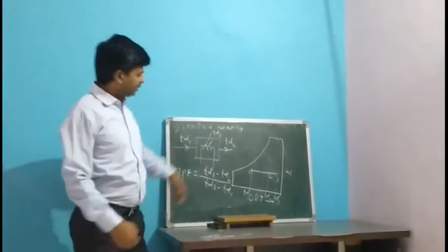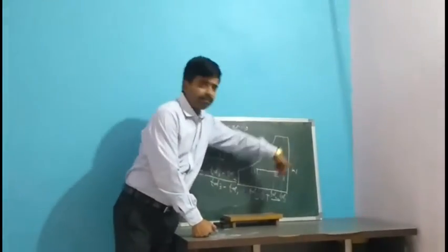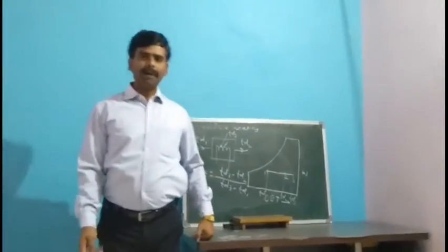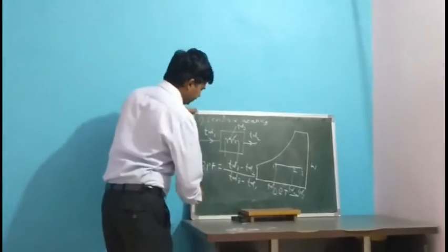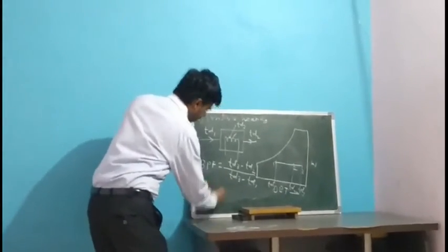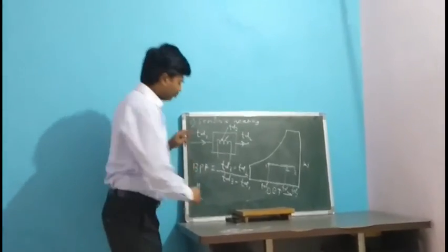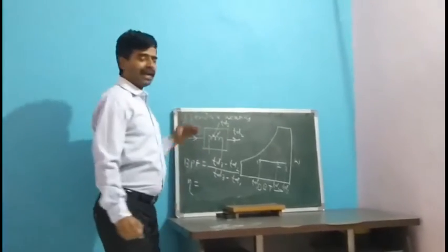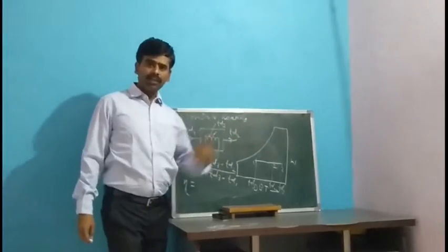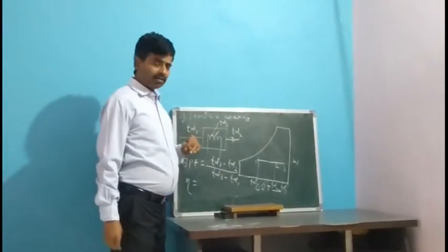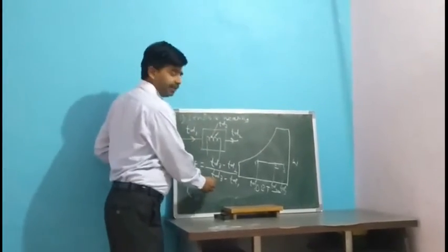Okay, so this is the unachievable heating effect because some of the air bypasses over that heating coil. Similarly, we can find out the efficiency of that heating coil. The efficiency of the heating coil is the actual amount of heat that gets transferred from the heating coil to the air. That is very simple, m dot Cp delta T.